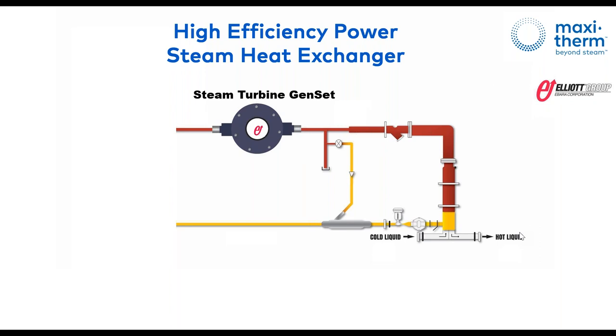And then we're losing power, right? Everything shuts down, power grid failure, whatever reason. Your generator is going to turn on. But also, we open a valve automatically to dump clean water to drain temporarily at 140 Fahrenheit, to increase the steam load and generate more power. So you have a pretty neat backup generator here, which is an automatic valve to drain, and your turbine will generate savings all year round. So there's another way of seeing it also.